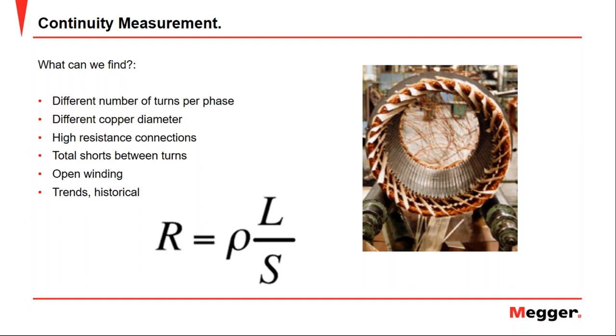Different number of turns per phase. If we have a different number of turns, we will have a different length per phase and therefore variation in the resistance. We can also find a different copper diameter, high resistance connections, total shorts between turns, open windings, and of course, the most important and critical point, we have to build trends, because with trends, we are able to avoid catastrophic failure.